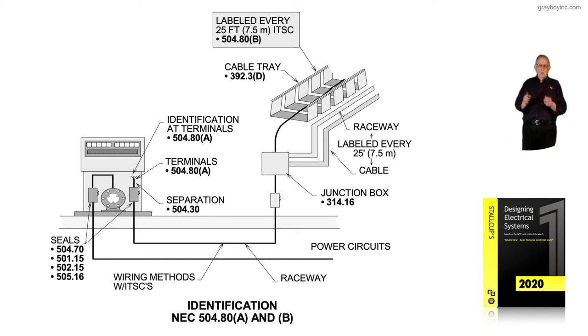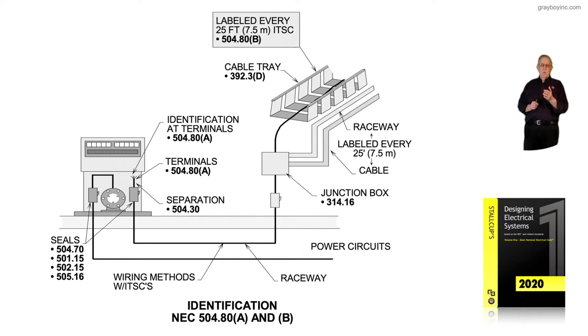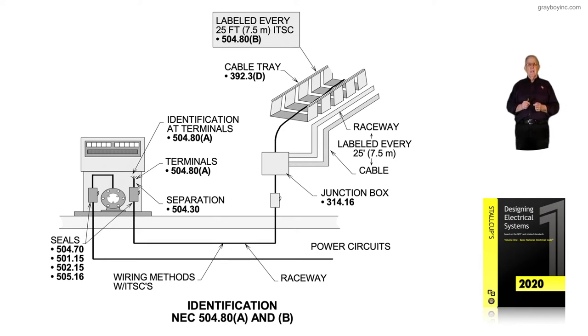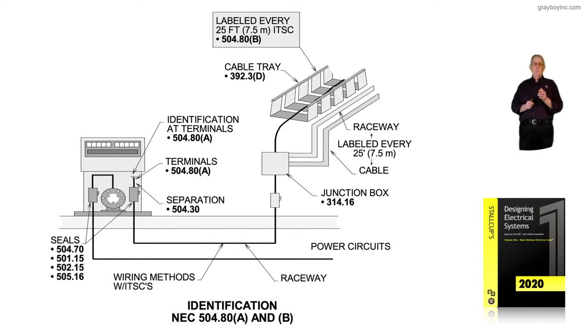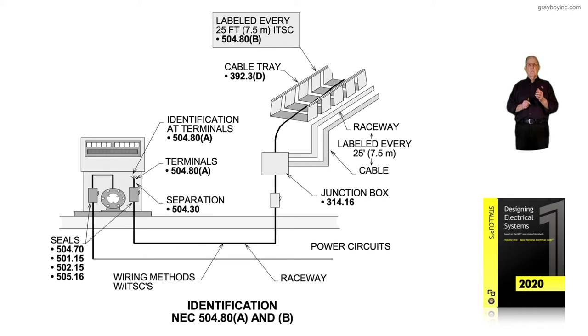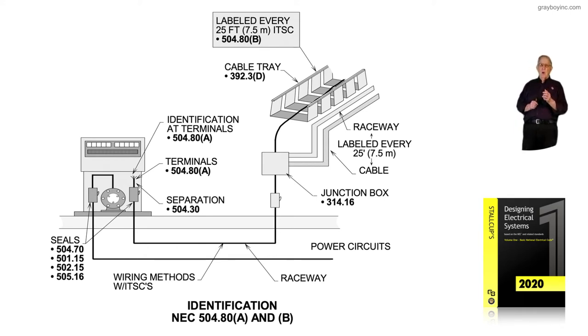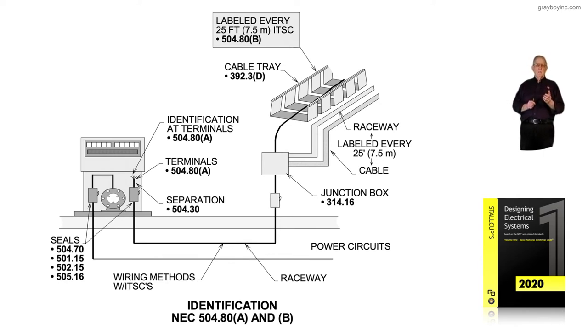Or a label could be put on them. Or you could route them inside the cable tray and put that label on the cable tray per 504.80 B, as you see there. The installation of the cable tray with these type of circuits is 392.10 C. And then you see we have the terminals going into the equipment, 504.80 A.